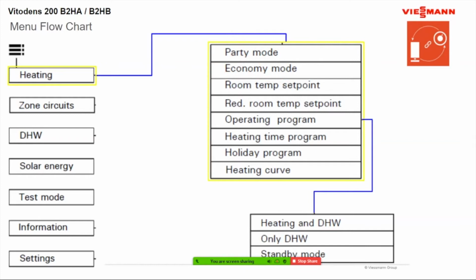Room temperature set point, remember that's if you're doing your heating circuits that way, you would set the temperature of your room temperature set point there, as well as you can do it on the main screen. Remember in the house, we saw that 70 with the arrows up and down. Or you can come to your heating menu and do it here. And I was jokingly earlier saying the red room, what that stands for is the reduced temperature. So reduced room temperature set point.